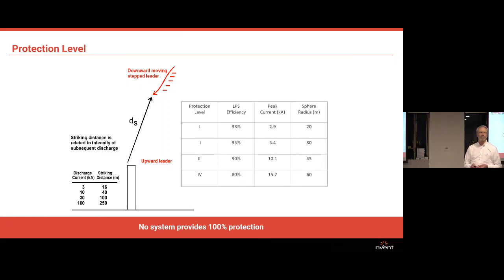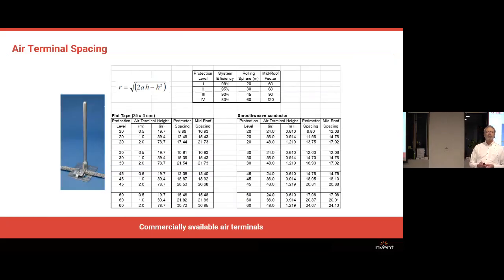The table on the bottom left tells you what current you can expect from the different protection levels and what distance they would cover. First of all, I'll say that the New Zealand standard recognises just vertical rods, such as in that picture. Overseas standards often recognise a conductor laid on the building, a Faraday cage type of arrangement, but flat on the building, and that's not recognised by the New Zealand standards. So we get engineers coming over here from the UK who are all excited about putting flat tape all over a building, and then they find it's not compliant with our standard.